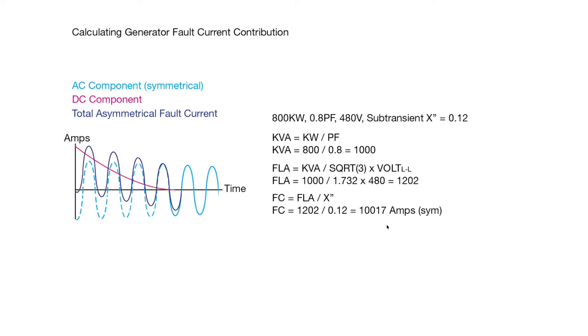So in this case we would need a circuit breaker or fuse that has an interrupt rating above 10,000. And we want to always add in a little cushion, so maybe we'd have something that was, if it was a circuit breaker, perhaps a 14,000 interrupt rating, or a fuse that probably is much higher anyway, so it's probably not an issue.